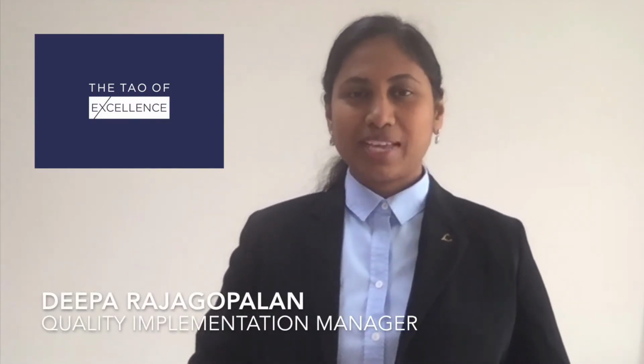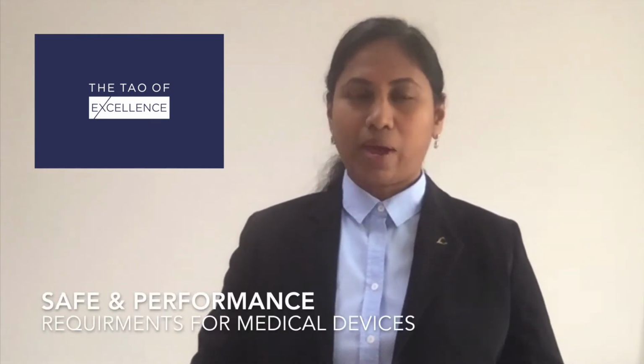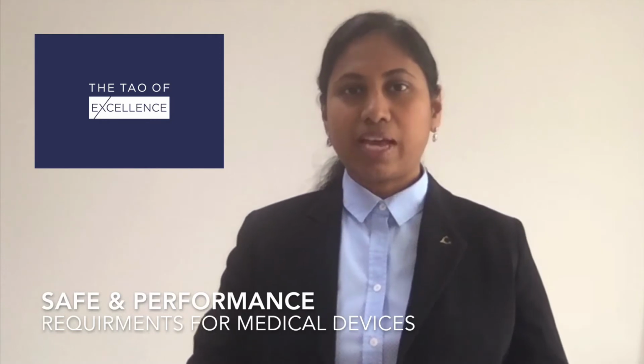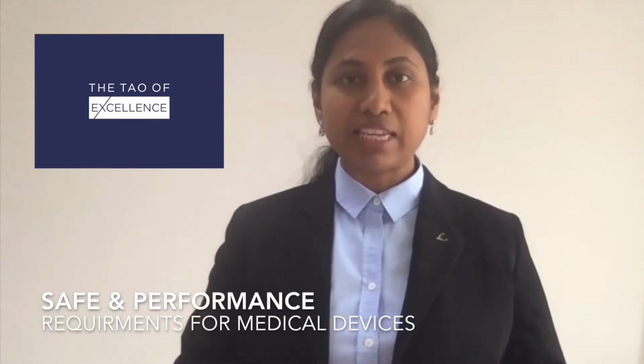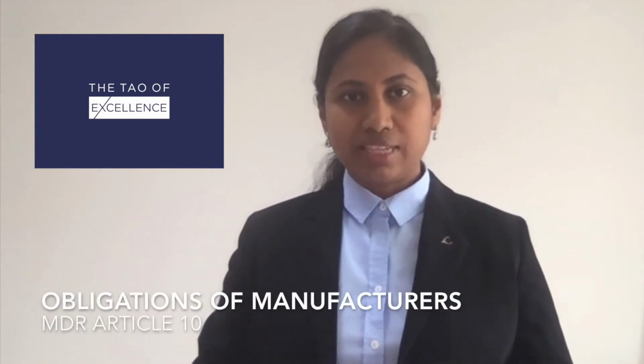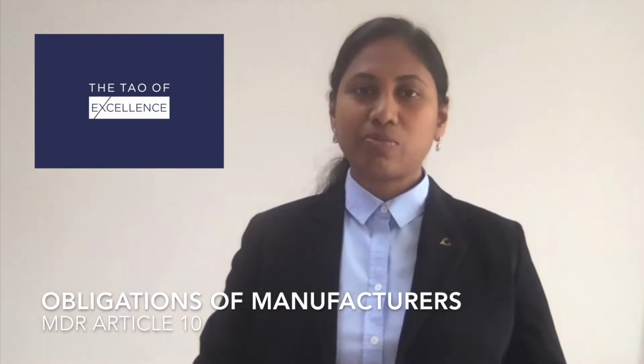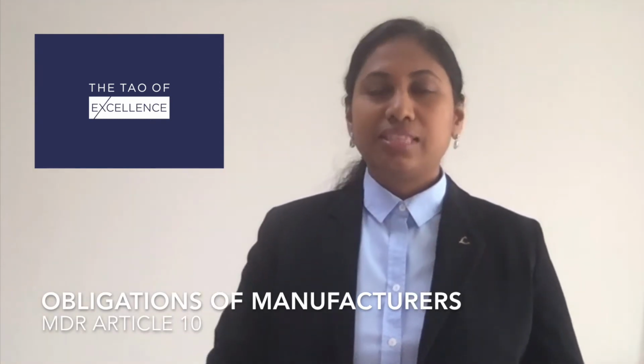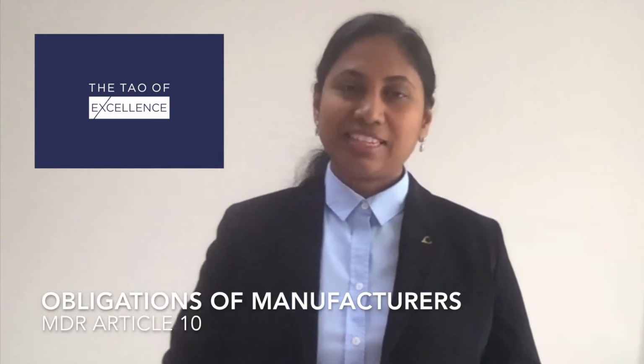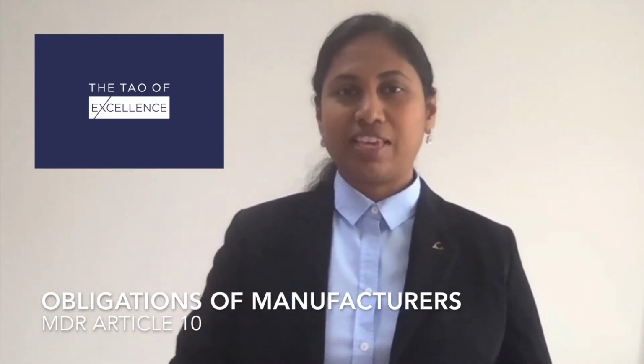Hello everyone. Today we look at one of the most important economic operators in the series, the manufacturer. The manufacturer has a significant responsibility to ensure that the device that is placed on the Union market conforms to the general safety and performance requirements. And this is achieved by setting up, implementing, and maintaining a set of systems like the risk management, the quality management, the CAPA system, the complaints management, etc. These responsibilities are explained in detail in Article 10 of the MDR.